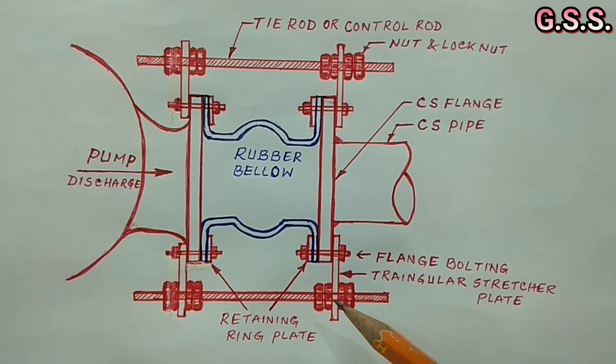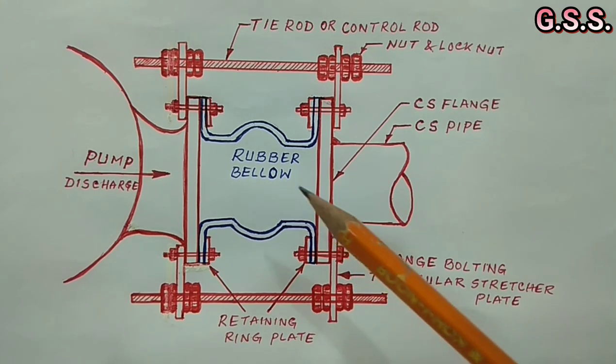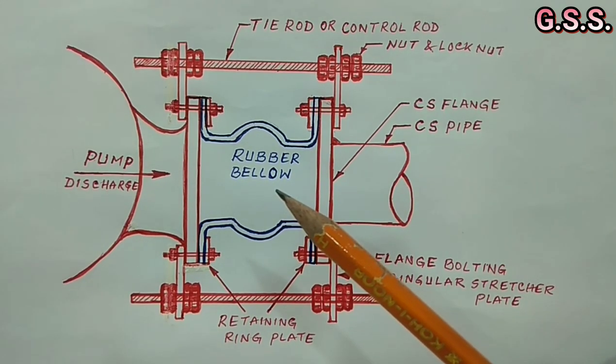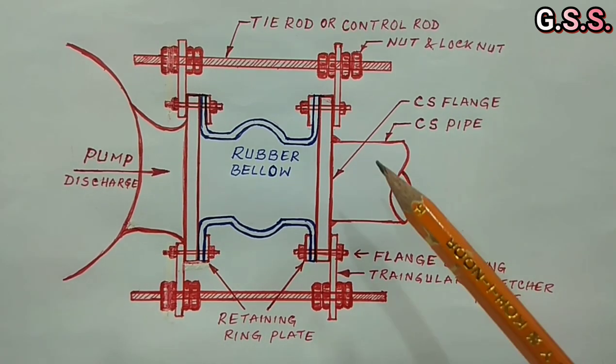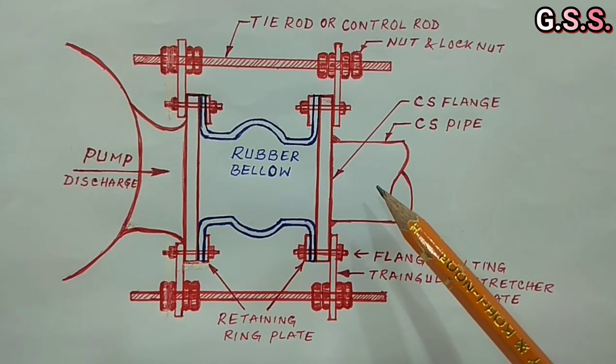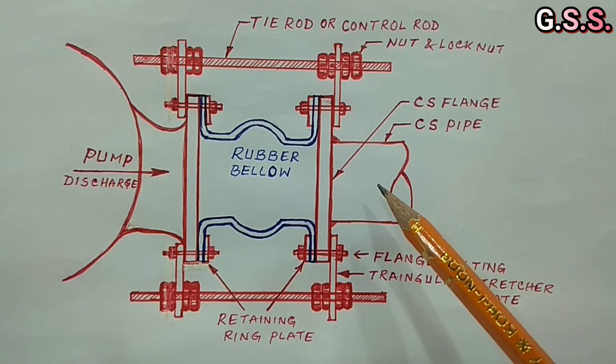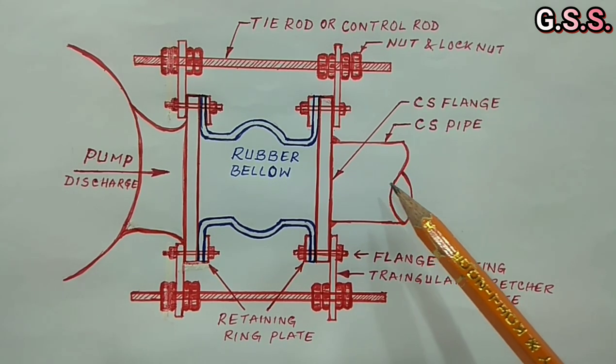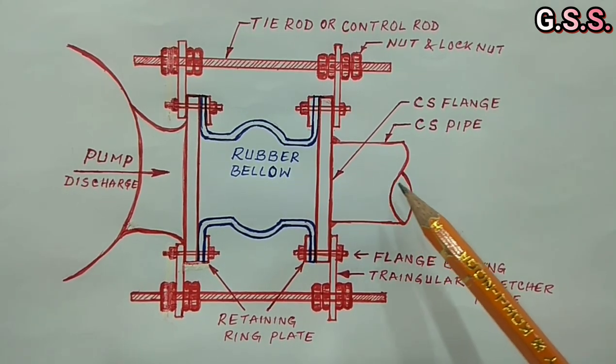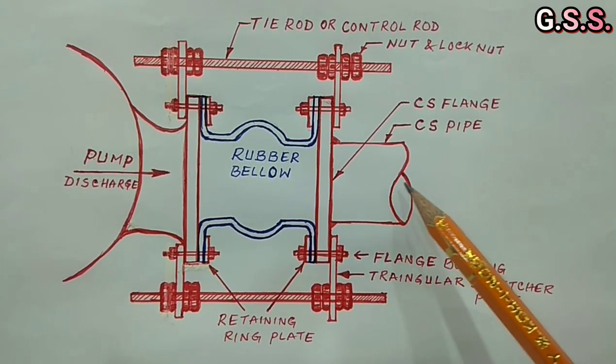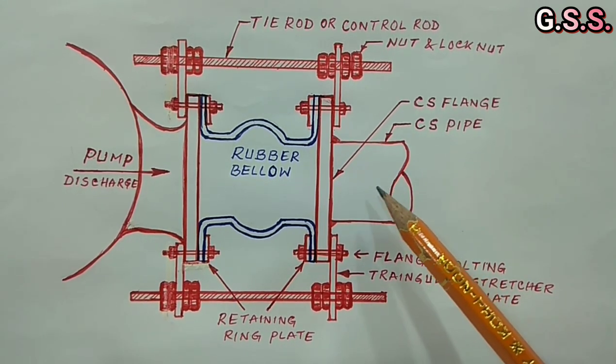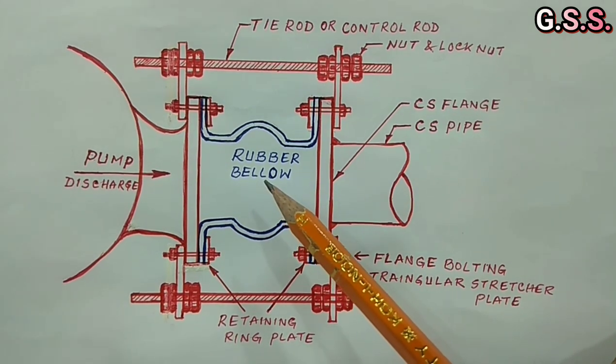Now, bellow installation is complete and we can start the pump. When pump operates, pipeline is pressurized along with the bellow. Due to internal pressure, there will not be any axial pressure thrust in steel pipe because steel pipe is axially very rigid but the bellow is not axially rigid.